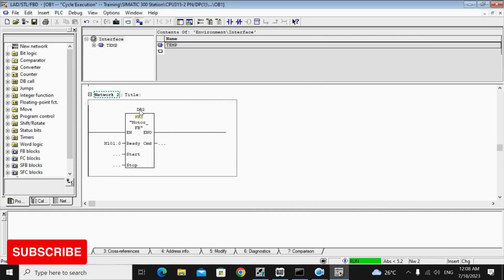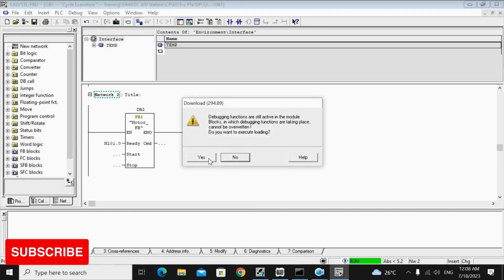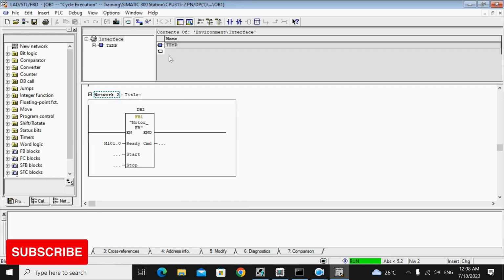It is reinitialized, because earlier the stop signal initial value was false, now we have changed it to true, so the DB value also changed, so you have to reinitialize the DB. Just click on that and press enter, it will reinitialize and the error will go away. Now download, monitor.